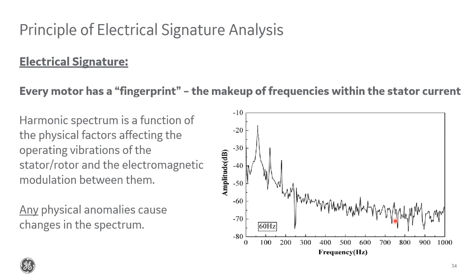So if you take the current signal, transform it from the time versus current domain to frequency versus the magnitude of those frequencies, otherwise known as doing the Fourier transform, you get something like this, where you can see the largest component of the signal is the 60 Hertz fundamental, but you also have all these other components of varying smaller magnitudes. And in a perfect world, you would just have a 60 Hertz signal and all of the rest of these would be flatlined. But in reality, every motor is built slightly different at a magnified level. There's going to be some sort of normal sounds, normal operating vibrations, and the exact relationship between the rotor and how it rotates within the stator, the current modulation between them. All of this will affect the makeup and the magnitudes of the harmonics that you would see here.